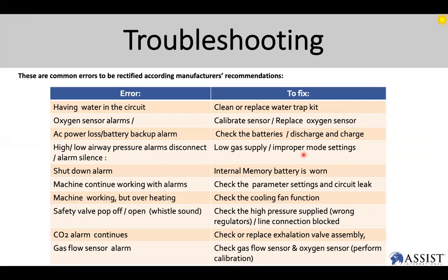Here's a troubleshooting chart with some commonly found errors on ventilators. If there is water in the circuit, you want to clean or replace the water trap kit. Also, if there is excessive water in the circuit, you can consider increasing the fresh gas flow. If there's oxygen sensor alarms, you want to go ahead and calibrate the sensor. And if that does not work, you want to replace the oxygen sensor. If there is AC power loss or battery backup alarm, you want to check the batteries, discharge, and charge the batteries.